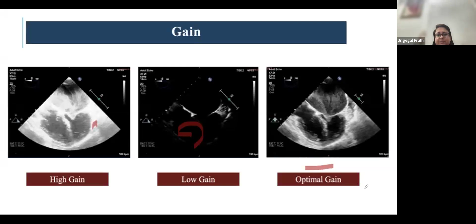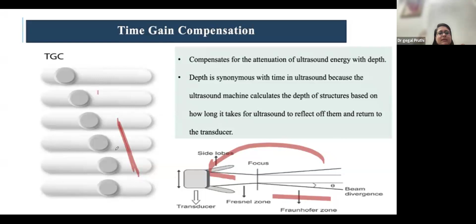Time gain compensation is called so because as the structures are deeper, the machine receives weaker signals back. So to compensate for the weaker reflected signals, we use time gain compensation. The higher settings are used for the far field structures based on the structure of interest. Mostly it is automatic in some machines, with this step ladder pattern. So here you can see with the step ladder pattern, far field structures are better seen.